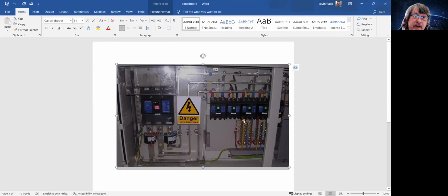So let's have a look again on the load side of the breakers. Here we can see a long stem bus bar, three connected there, red, white, blue. And from each one steps a cable and goes out to a small, I presume a small breaker somewhere in another panel, or maybe on the left or right of this particular panel. Now, when we have a look at that, of course, we said we had potentially maybe 20 kA here. All these products here provide protection all the way downstream to those small products.